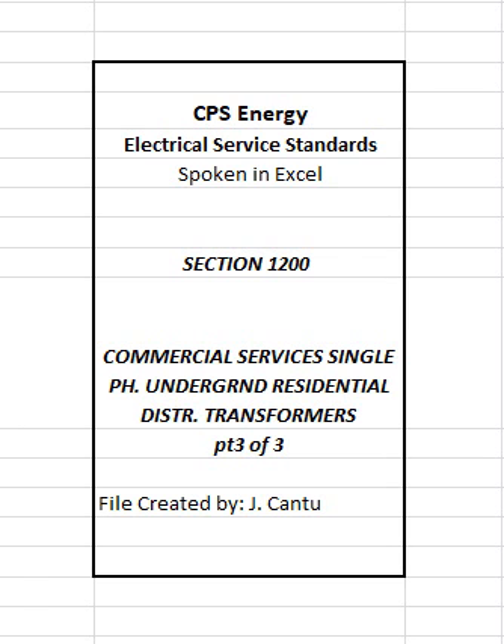1. Open access to transformer and any required pull boxes, both vertically and horizontally, by equipment and personnel. Where located behind a wall or fence, the wall or fence may not be taller than 8 feet and must include a minimum 6-foot wide opening in front of each transformer and pull box. 2. 15-foot wide, all-weather drivable surface up to transformer slab and pull box slab, if required, for access by CPS Energy equipment. Drivable surfaces shall meet the design criteria outlined by the CPS Energy Customer Service Representative.